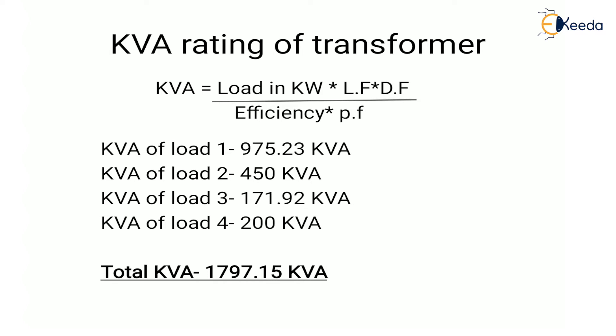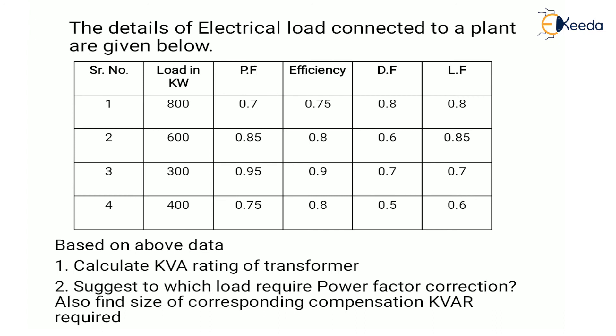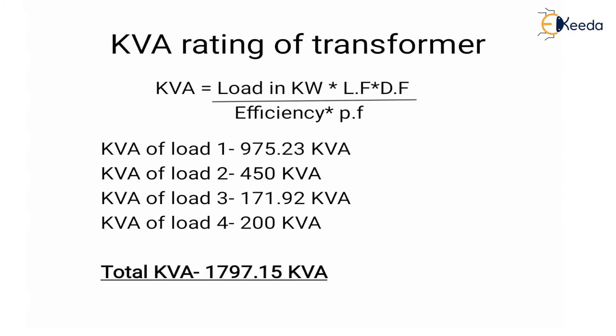To find out the KVA rating of a transformer, we have to find the KVA value of individual loads. The formula is: KVA = (load in KW × load factor × diversity factor) / (efficiency × power factor). For load 1, KW is 800, so: 800 × 0.8 (diversity factor) × 0.8 (load factor) / (0.7 (power factor) × 0.75 (efficiency)) = 975.23 KVA.